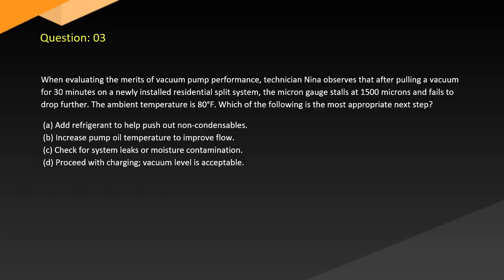Question 3. When evaluating the merits of vacuum pump performance, technician Nina observes that after pulling a vacuum for 30 minutes on a newly installed residential split system, the micron gauge stalls at 1500 microns and fails to drop further. The ambient temperature is 80 degrees Fahrenheit. Which of the following is the most appropriate next step? A. Add refrigerant to help push out non-condensables. B. Increase pump oil temperature to improve flow. C. Check for system leaks or moisture contamination. D. Proceed with charging. A vacuum level is acceptable.